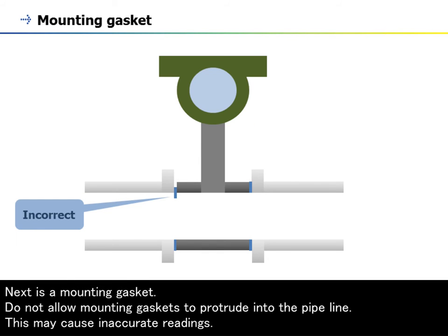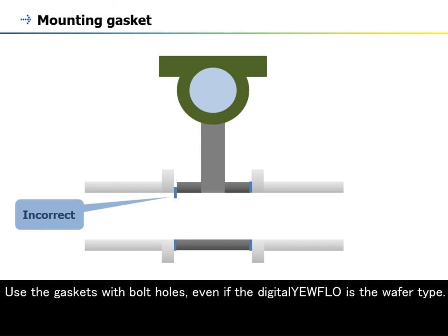Next is a mounting gasket. Do not allow mounting gaskets to protrude into the pipeline, as this may cause inaccurate readings. Use the gaskets with bolt holes, even if the digitalYEWFLO is the wafer type.